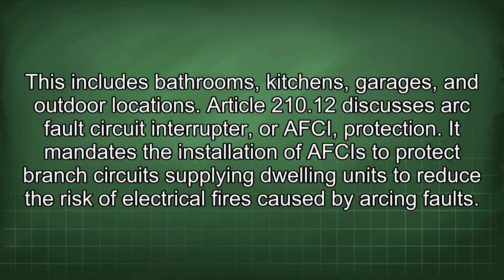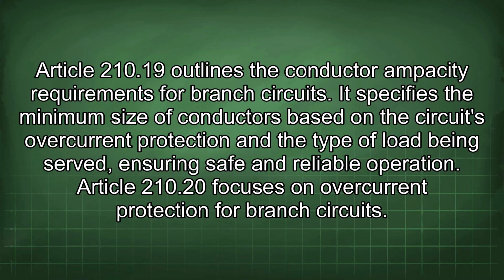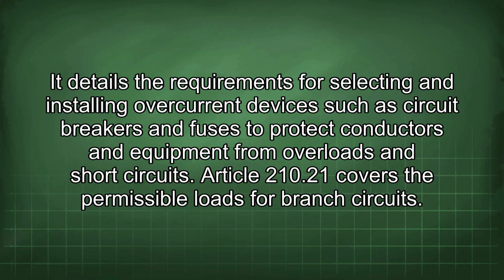caused by arcing faults. Article 210.19 outlines the conductor ampacity requirements for branch circuits. It specifies the minimum size of conductors based on the circuit's overcurrent protection and the type of load being served, ensuring safe and reliable operation. Article 210.20 focuses on overcurrent protection for branch circuits. It details the requirements for selecting and installing overcurrent devices such as circuit breakers and fuses to protect conductors and equipment from overloads and short circuits.